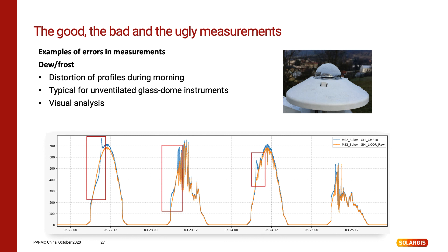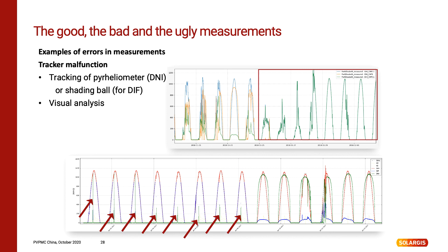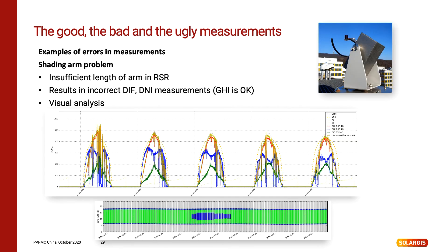We need the sun to evaporate dew. Ventilation units or heated domes may help to remove this issue. These pictures illustrate the situation of moving parts where the sensor tracker lost power or got stuck. Usually it is the case of pyrheliometers or diffuse pyranometers shaded by a shading ball. In both cases, diffuse will be equal to global irradiation and DNI is not measured or measured only as peaks. Another type of mechanical problem is the insufficient length of the shading arm mounted on an RSR. In this case, during a certain period of the year, the sun was in a position where the rotating arm of the RSR was not able to create a shadow over the sensor, so diffuse measurements were distorted.